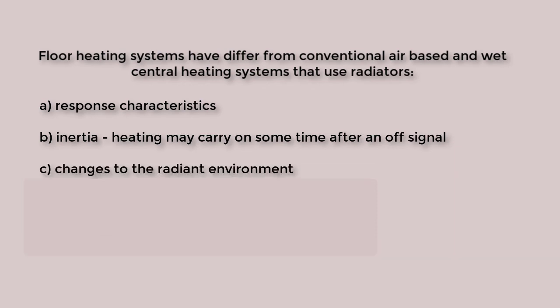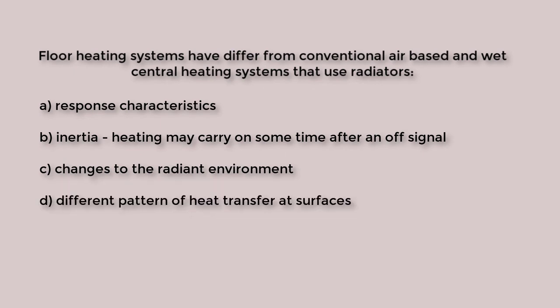A large area of moderately warm temperature changes the radiant environment in the room and thus the perception of comfort. Whilst air-based systems will initially drive a change in air temperature followed by changes in surface temperatures, radiant heating will distribute heat directly to other surfaces by way of radiating exchanges as well as to the air adjacent to the heated surface by way of convection.